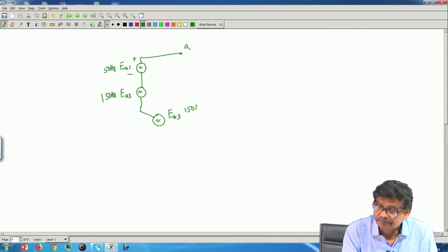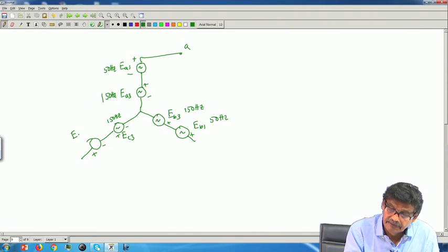Then E B 1 is the fundamental component at 50 hertz, and finally this C phase: E C 3 is the third harmonic component at 150 hertz, and then the fundamental component E C 1 at 50 hertz. This is your B terminal going towards the load C terminals. Similarly, in the primary coils, do not worry about that.